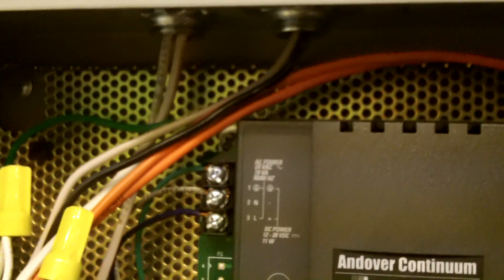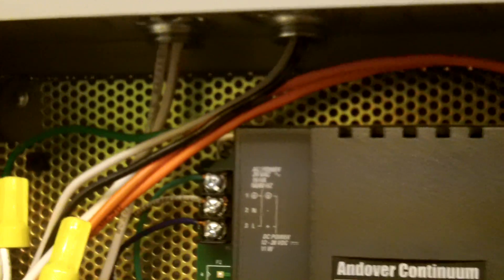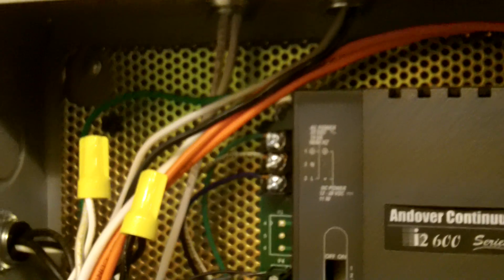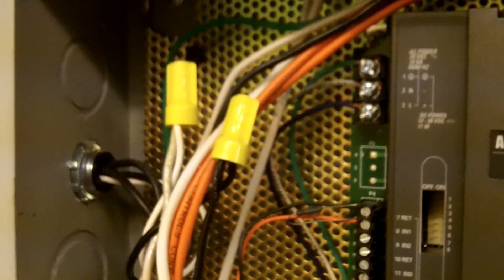There's also another exception that would allow both these types of circuits in the same enclosure if they are routed to maintain quarter-inch separation. And as you can see, neither of those has happened here. So we've got a violation of 800.133A1D.